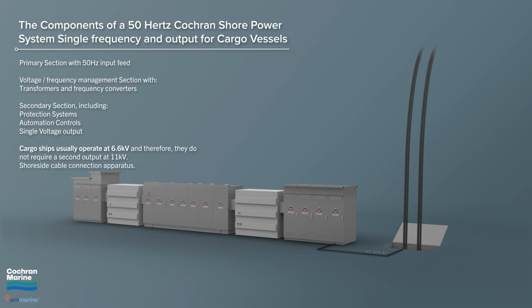Cargo ships usually operate at 6.6 kV, and therefore they do not require a second output at 11 kV. The system also includes the shoreside cable connection apparatus.